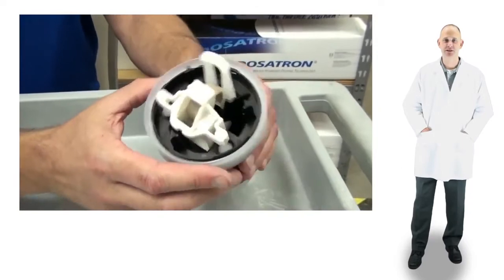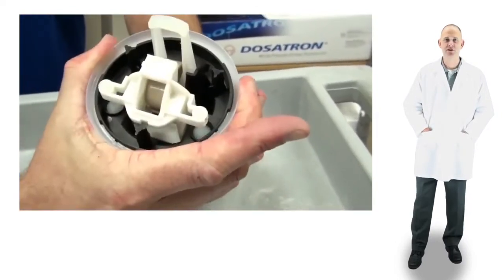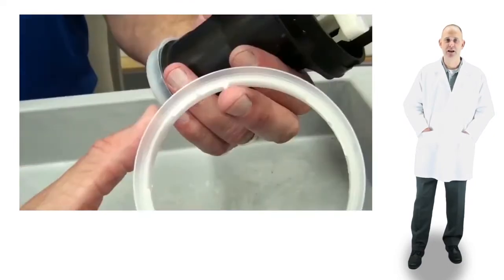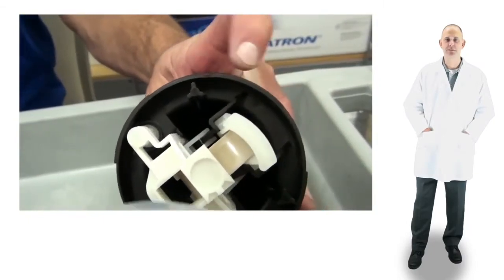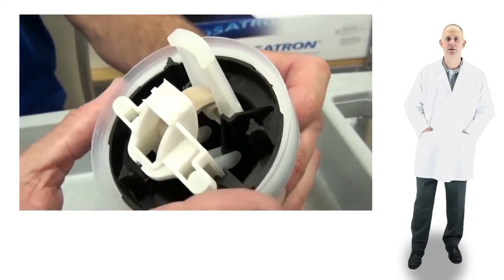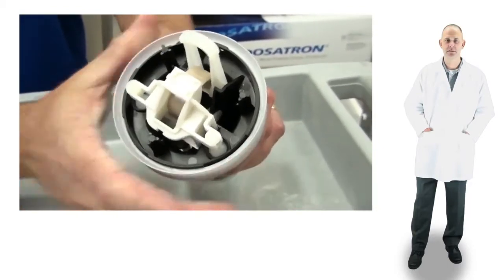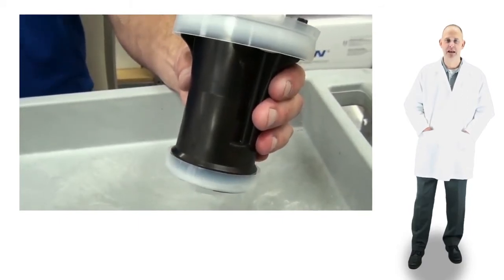To replace the flanges, grasp and twist counterclockwise. Remove by lifting straight up. To reinstall, align the tooth inside the flange with the notch in the piston shell. Press it down into place and twist clockwise until it locks. The procedure is the same for the top and bottom flange.